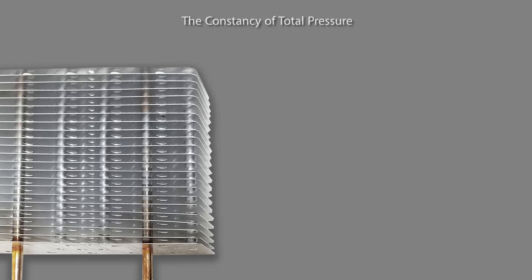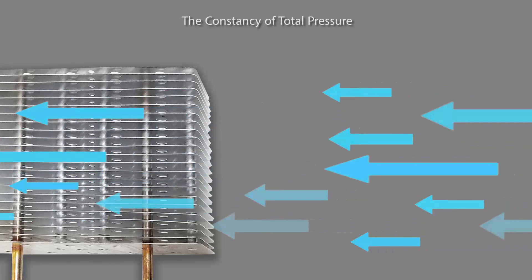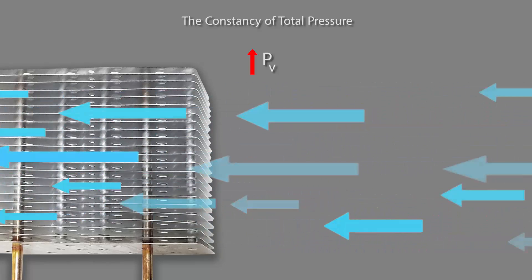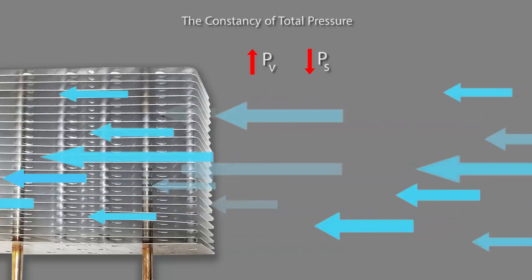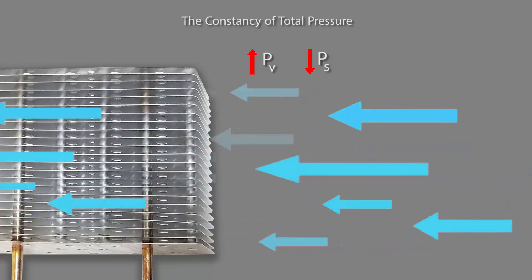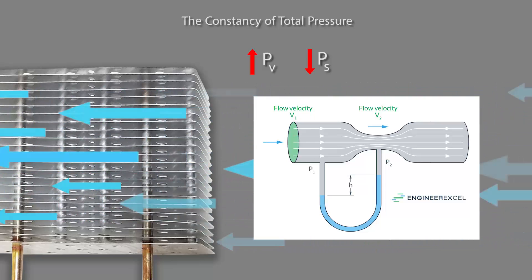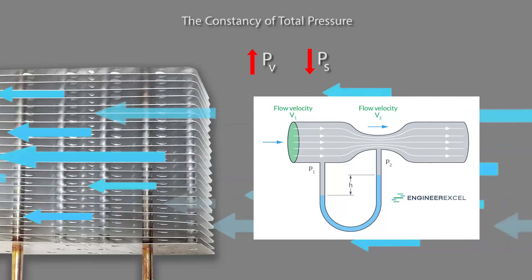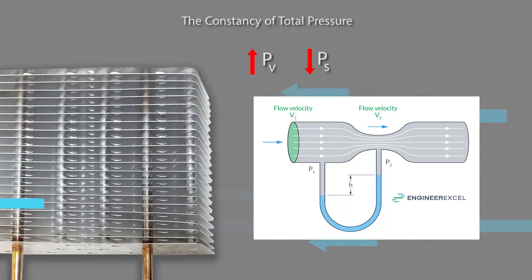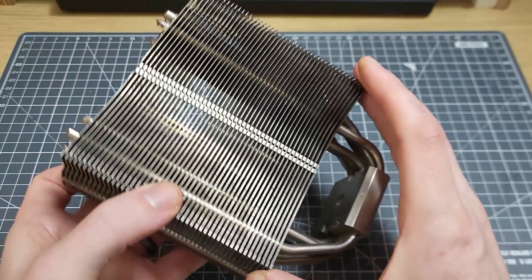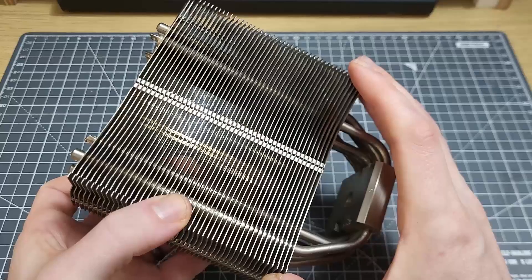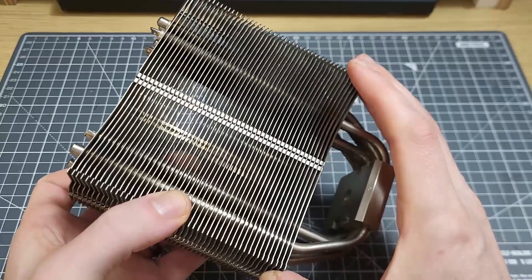When air is pushed through the fins of the heatsink there will be an increase in velocity pressure and a decrease in static pressure. This phenomenon is akin to the venturi effect which is a working example of Bernoulli's principle. We are therefore able to infer that a given level of airflow through each cooler will be different in the following ways.